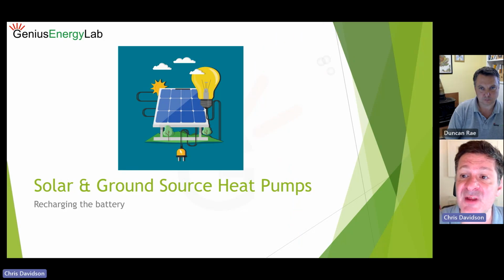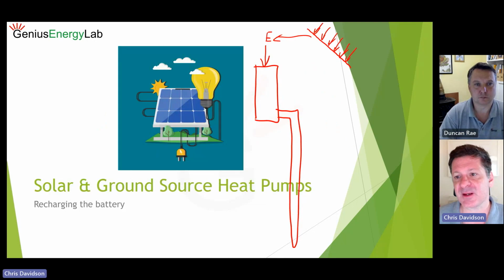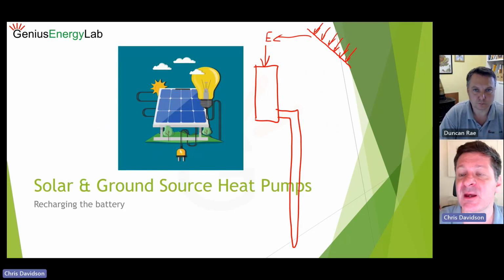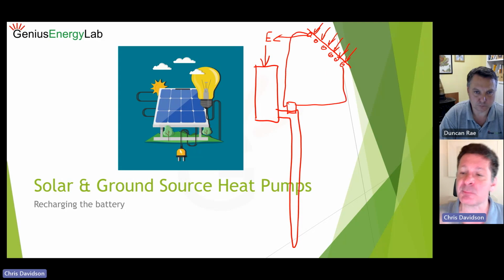What you can then do is, instead of just going for solar PV, we can go with solar PVT, photovoltaic thermals. It's got a backing on the PV panel of a solar thermal element. And via a heat exchanger, we can connect that up to the ground loop and put heat into that ground loop. Now that has a massive efficiency uplift on that heat pump system. So from that typical 3.5 to 4 seasonal COP, we've got a system running in Cardiff. It's been running for a couple of, 3 years now, and that's up at 5.5 seasonal COP. So massive efficiencies. And because you're cooling that solar PV panel, you're increasing the electrical generation efficiency by something like 25%. So it's a win-win in all regards.